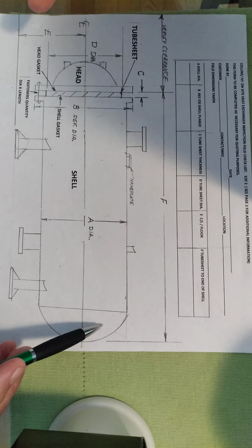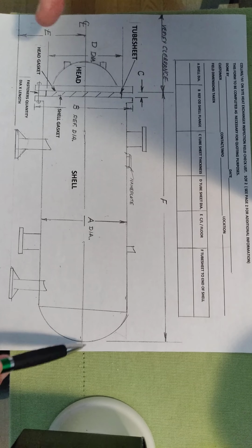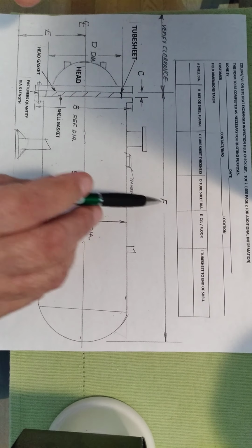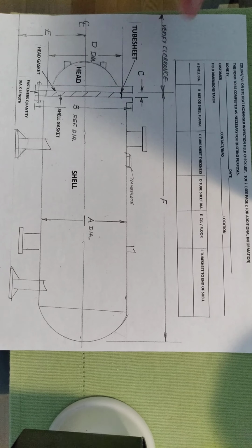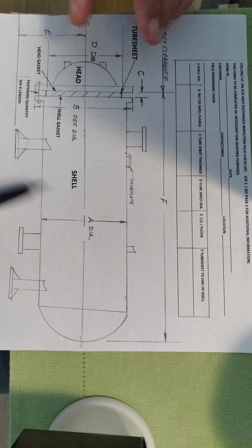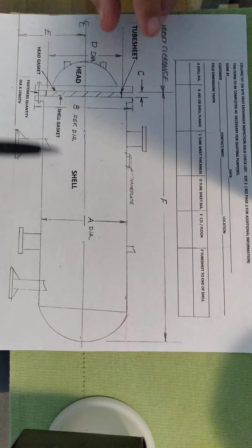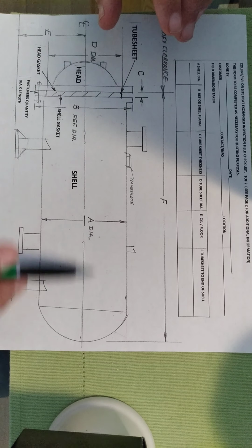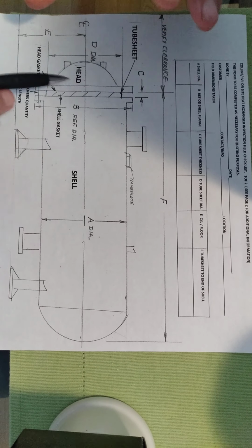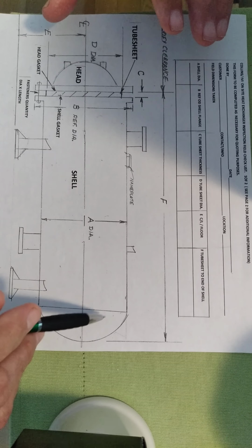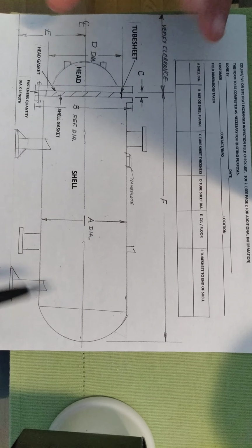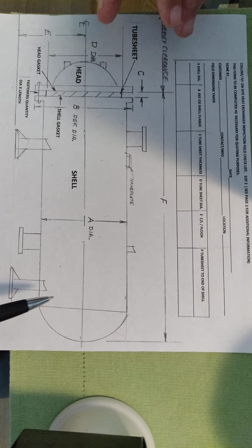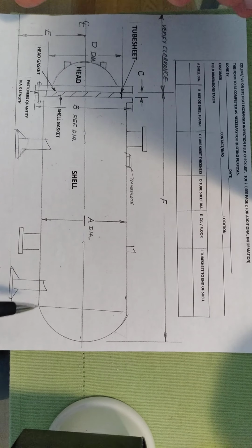For quoting purposes, I'll usually subtract 2 or 3 inches from what the dimension actually is, figuring that's the longest back to end tube you can have or physically get in the unit. So that helps for quoting purposes. So we'll quote X amount of tubes, say 85 inches long, and longest back to end being 85, and then the thickness of the tube, they just go down from there. But it gives us a good fundamental quoting pinpoint area.